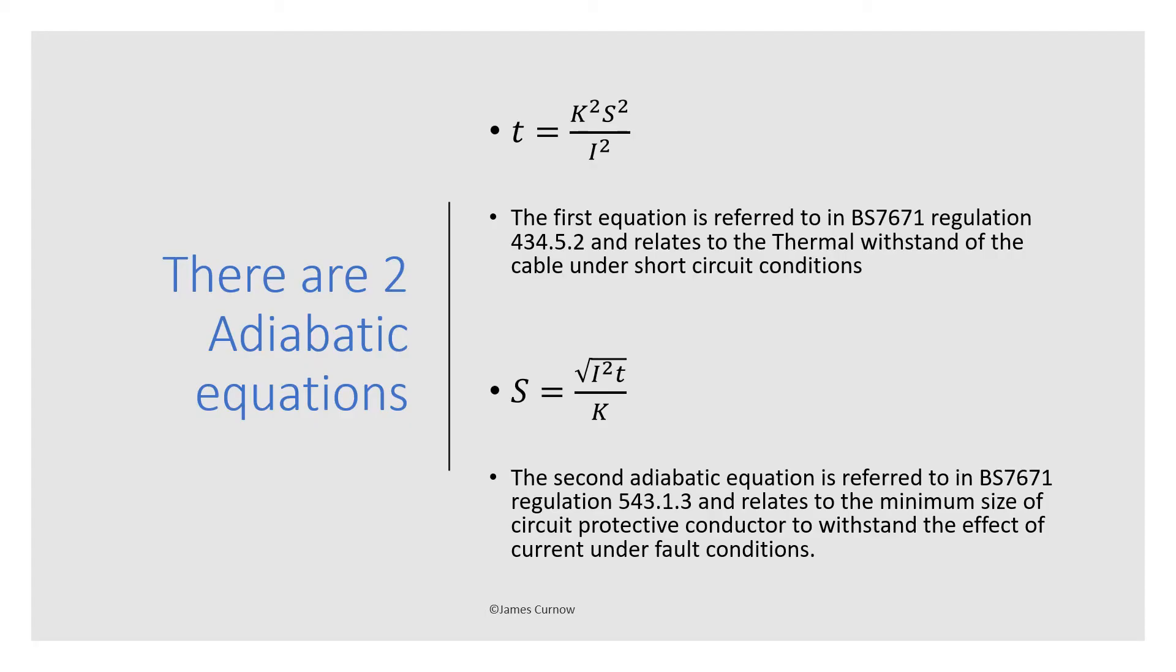The first thing to point out is that there are actually two adiabatic equations and they're both mentioned in different sections in the wiring regulations but I find it useful to explain them together. The first equation is referred to in BS7671 regulation 434.5.2 and this relates to the thermal withstand of the cable under short circuit conditions, either line to neutral or line to line in three phase.